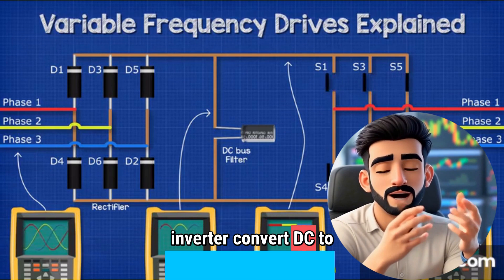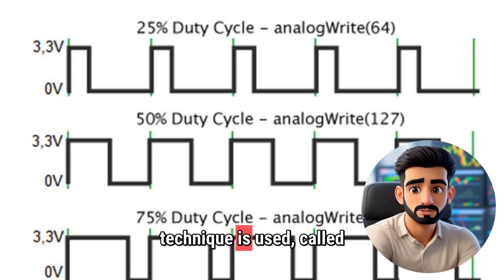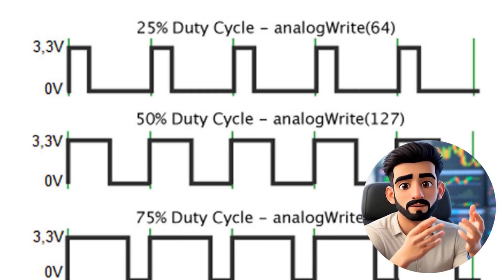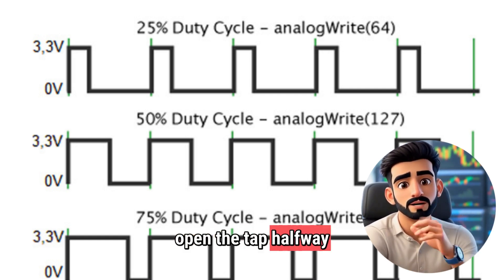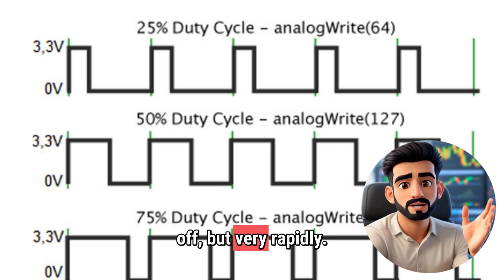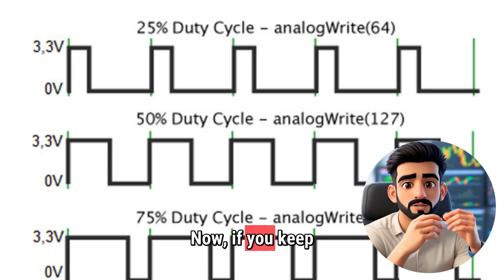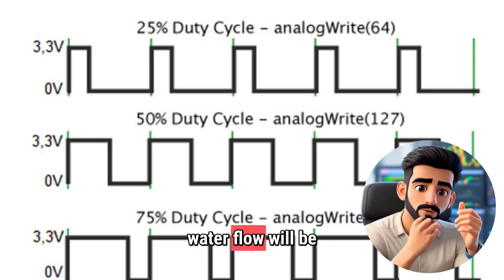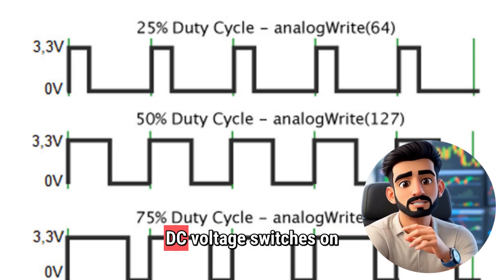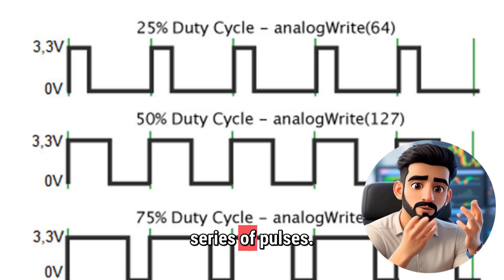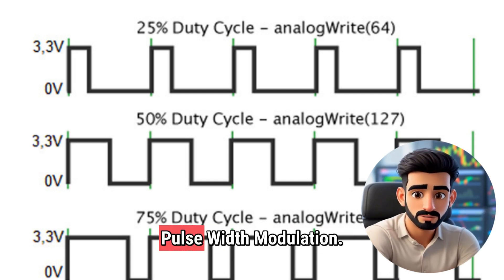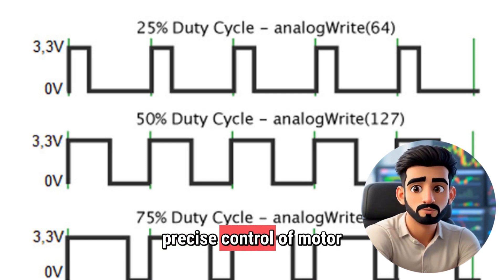But how does the inverter convert DC to controlled AC? Here, a very popular technique is used called Pulse Width Modulation, or PWM. Let's understand it in simple language. Imagine you have a water pipe with a tap and you need to control the water flow. One way is to open the tap halfway. PWM works differently: it turns the tap fully on and fully off, but very rapidly — thousands of times per second. If you keep the tap on for more time and off for less, the average water flow will be higher; keep it on for less time and the average flow decreases. The inverter does exactly the same — it rapidly switches DC voltage on and off, creating a series of pulses. By adjusting the width of these pulses, that is the on-time, it controls the average voltage and frequency supplied to the motor. That's why it's called Pulse Width Modulation. With this technique, very precise control of motor speed and torque is achieved.